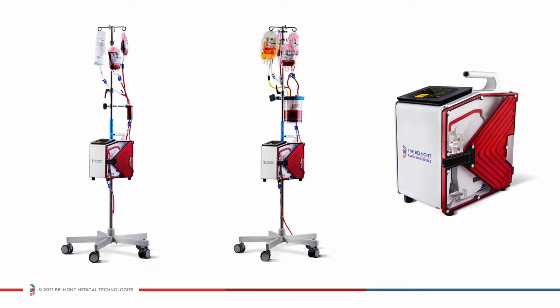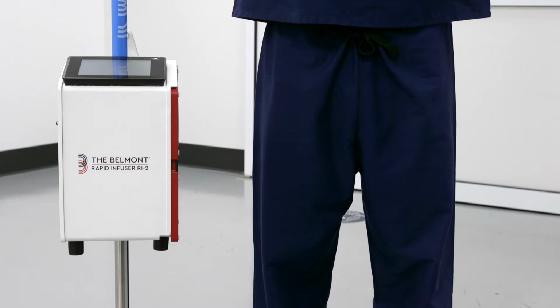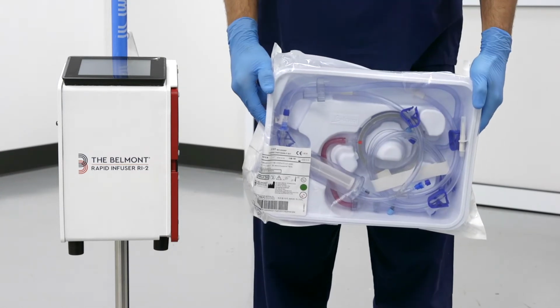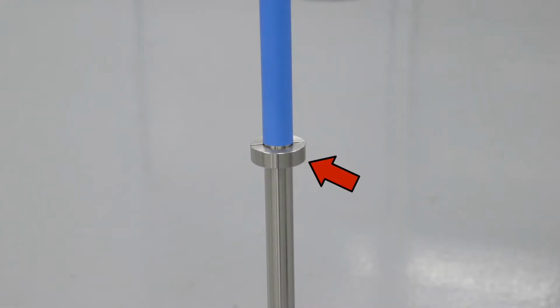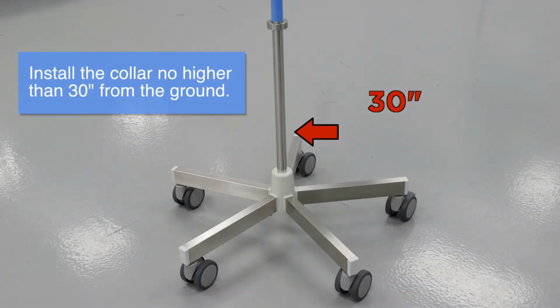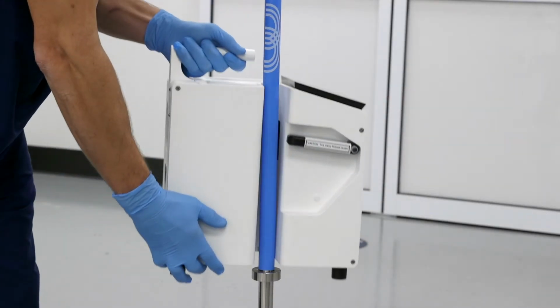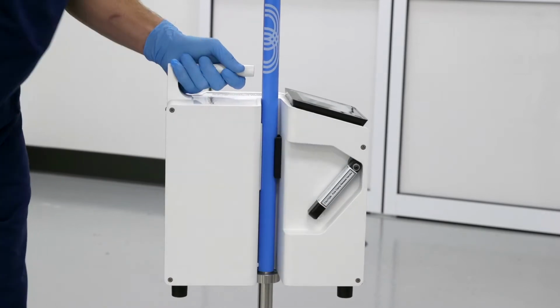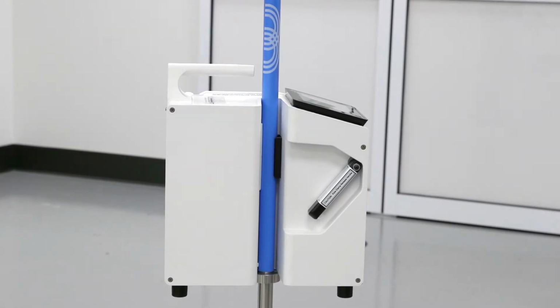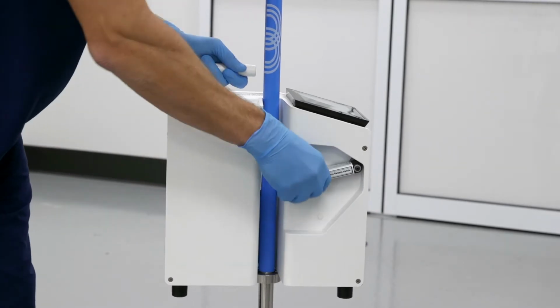The Belmont Rapid Infuser RI-2 consists of two main components: the control system, which is mounted on an IV pole, and the disposable set. First, install the collar on the IV pole just beneath the system, no higher than 30 inches from the base of the IV pole. Mount the system above the collar by pushing down on the pole release handle. Check that the system is secure before proceeding. To remove the system, lift up on the pole release clamp while holding on to the top handle. This will prevent the system from falling.